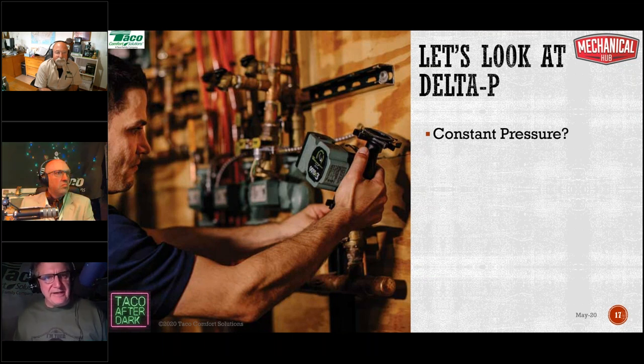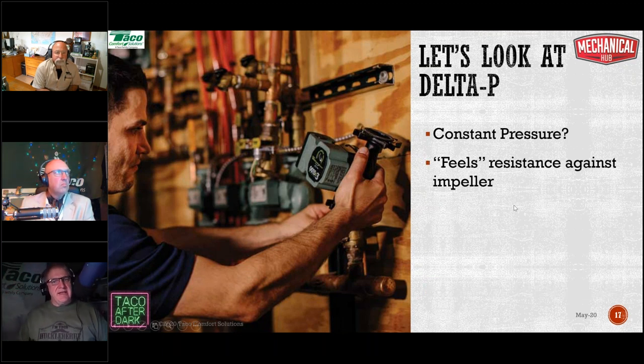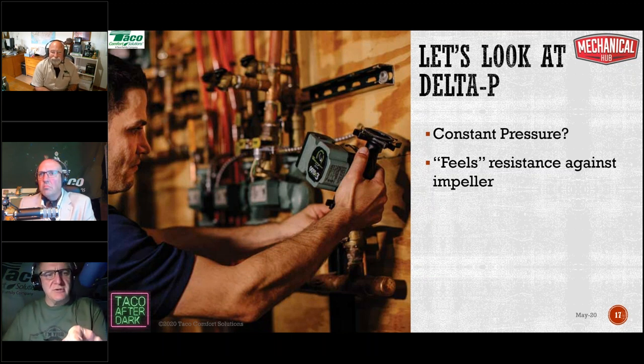So say you have it set up for 10 feet of head. Zone's open, the pump's going to go faster. Zone's closed, the pump's going to go slower, but always along that 10 foot of head constant pressure performance line. System curves and pump curves, people, it has to do that. So it's going to work on that prescribed line. Now the trigger that tells this thing to speed up or slow down is resistance against the impeller. Let's say I've got 5 zones open and the impeller's spinning and having itself a grand old time. A zone closes, and all of a sudden that impeller is spinning against a little bit more resistance. The circulator thinks, hey, something must have closed, I don't have to run so fast. It slows down. That's all it does along that prescribed performance curve.